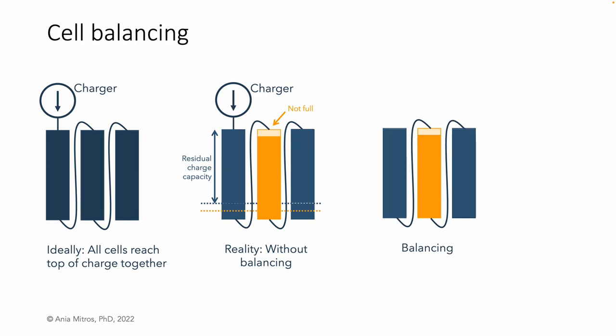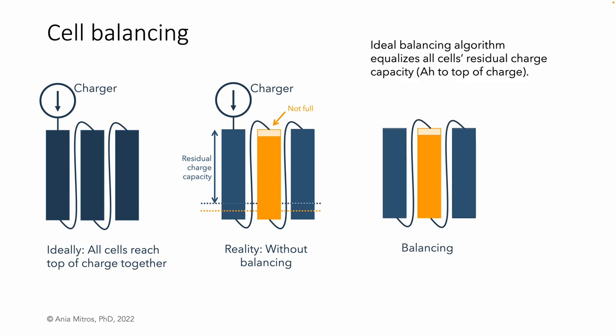Balancing restores the more ideal situation. An ideal balancing algorithm is one that results in all cells having identical residual charge capacity. Passive balancing does this by selectively discharging cells as needed so that their residual charge capacities match, or in other words, so each cell can take in the same number of amp hours before reaching top of charge.